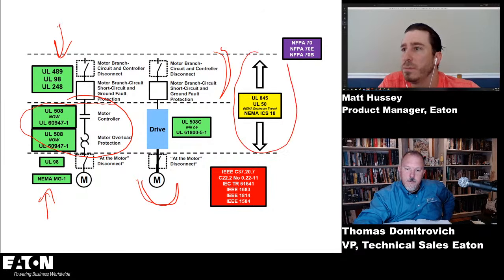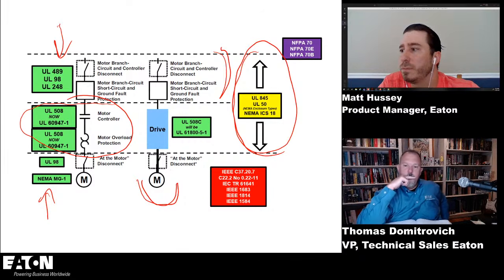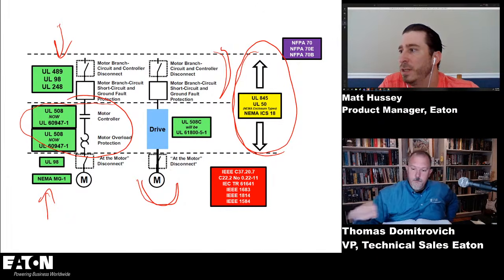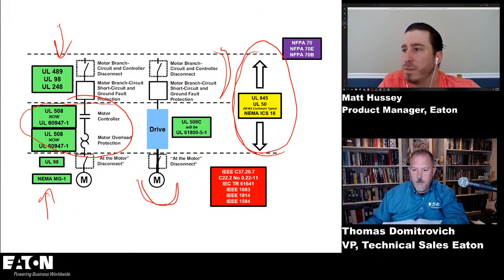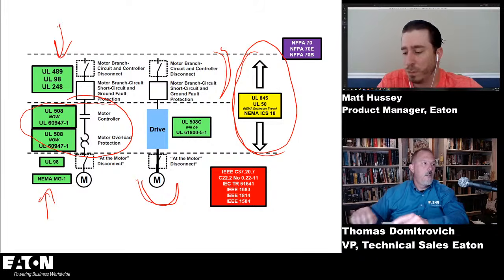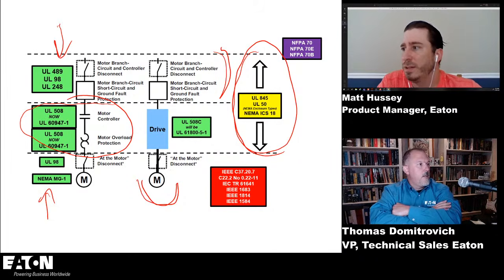So what about this over here? In reality, if somebody's out there specifying the equipment, pretty much those are going to be their main reference points. UL 845 is the standard that MCCs are tested to and listed. ICS 18 talks about how the equipment is constructed and things like that, but 845 outlines how it's tested. And then we've got environmental ratings. So you've got NEMA 1, 12, 3R, things like that. UL 50 outlines how you go about testing for those different enclosure types.